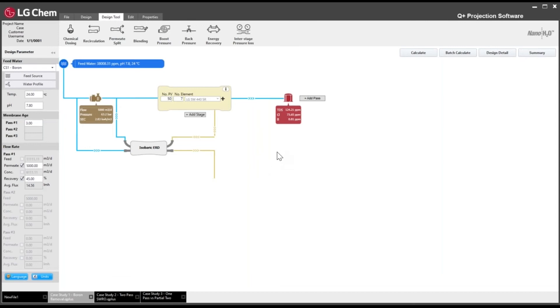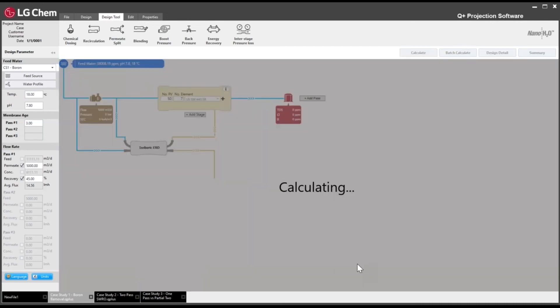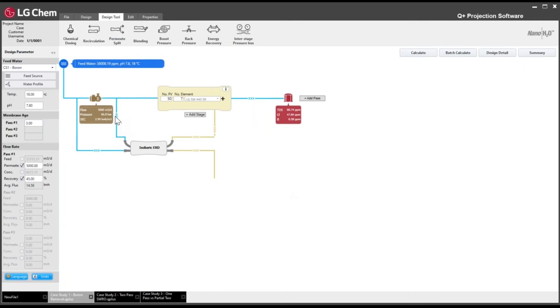Permeate TDS and chloride — 350 ppm and 200 ppm respectively — are easily met and no concern. We also want to check maximum feed pressure at the minimum temperature of 18°C. At 18°C, the calculation gives 66.8 bar operating feed pressure. This value, plus a safety margin and flow losses, is used to size the high-pressure pump.